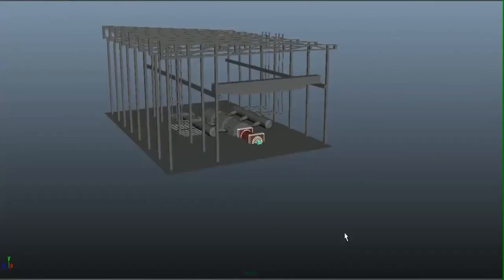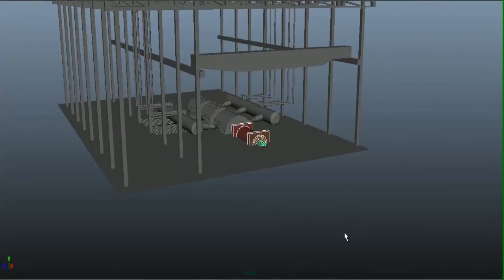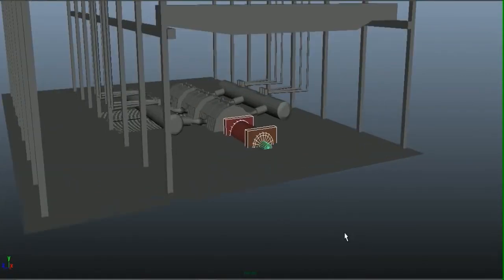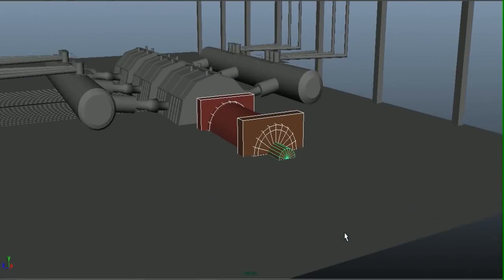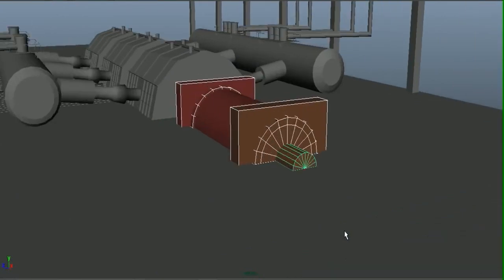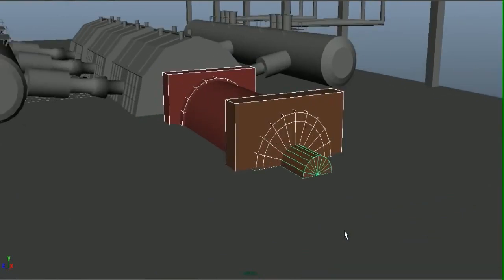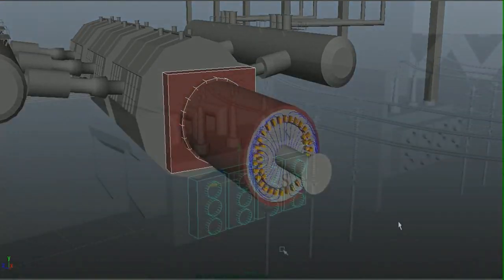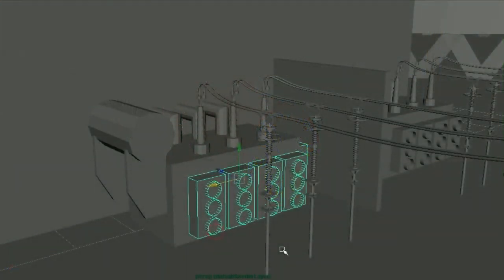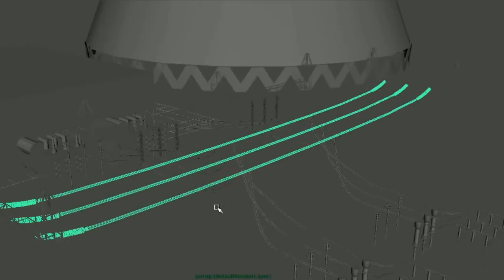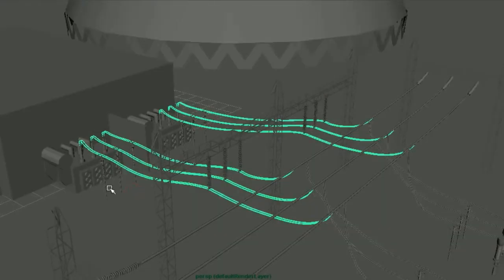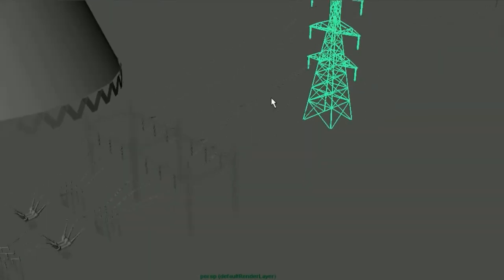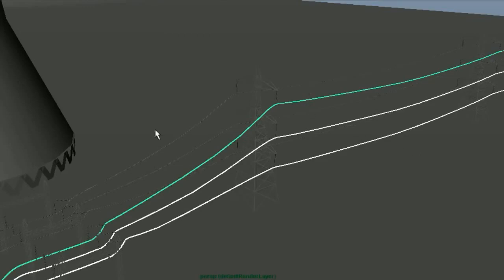As per Indian standards, the specified voltage limit for generation by 15 MW and above units is 11 kV, 13.8 kV, or 16 kV depending on the size of units. We can increase it up to a level of 66 kV, 132 kV, 220 kV, or 400 kV depending on the length of the transmission line.